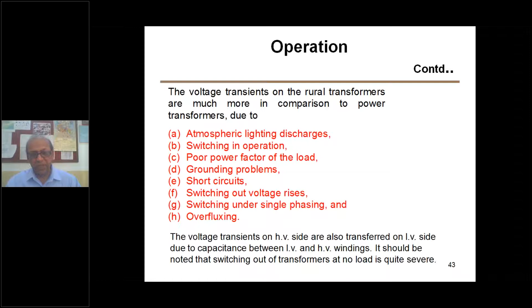So this is what we have discussed. No doubt, regular inspection and maintenance is important — I'm not discussing it in detail here — but everyone knows it matters, though it's only possible if you have a reliable transformer. If your transformer is failing at a rate of 10% or so, periodical checks become very difficult for such a huge number of transformers. It becomes impractical and too costly. Therefore, the inherent strength of the transformer must be good; once that is good, it becomes possible to do proper maintenance.